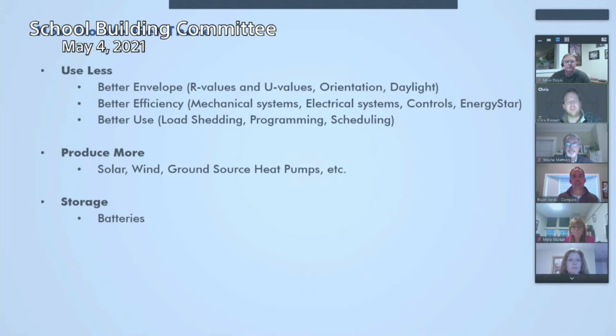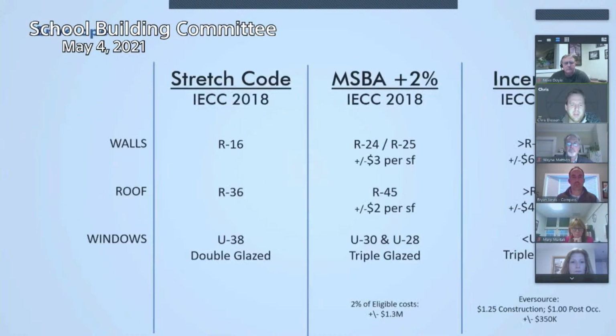With regard to the envelope, the stretch code implies you're going to have walls of a certain R value. R value is just thermal resistance, and the higher the R value, the better. So the R value is around 16 for walls, around 36 for roof, and windows 38 or better. The U value you want lower. So R value, the higher the better; U value, the lower the better. The amount of glazing you put in there helps with that as well. So stretch code is good, it's a really good program, way better than the base code.